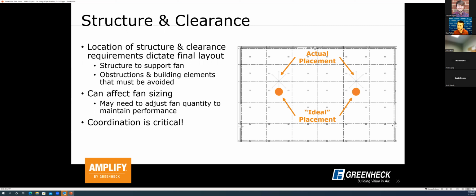So for example, you want to make sure that you don't have an HVLS fan directly below a light source, because that can create what's called a strobe effect, a flickering of lights that can be disorienting to occupants in the space. So looking at all those clearance requirements can be a very critical part of the design process, and it may affect some of your fan sizing, fan quantity, and even sometimes placement, like I mentioned previously. So again, coordination is really critical at this point, coordinating not only with your design team, but also potentially with the architect, electrical engineers, whoever else may be affected by some of these changes in where a fan is located in a space.